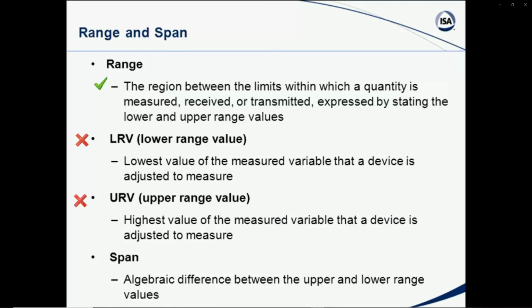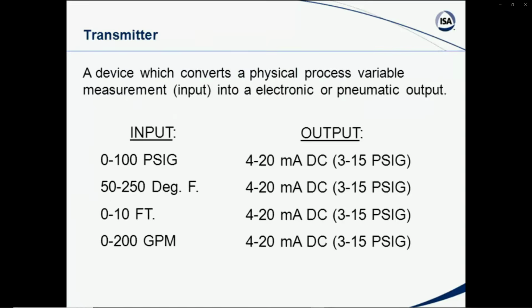And then if you get a question that refers to what is the span of a transmitter, that is the algebraic difference between the upper and lower range values. So that's simply the span from the lower to the upper, and it's just the algebraic difference because, again, if you go back and look at these particular situations, this pressure transmitter would have a span of 100 psig. The temperature would have a span of 200 degrees Fahrenheit. The level transmitter might have a span of 120 inches or 10 feet. And the same way with the flow measurement, the span would be 200 gallons a minute. Again, it is the difference between the upper range value and the lower range value.